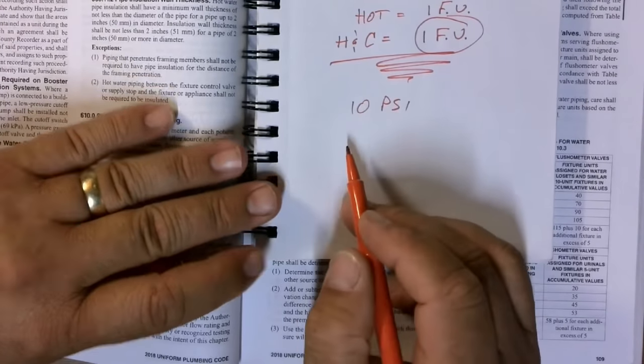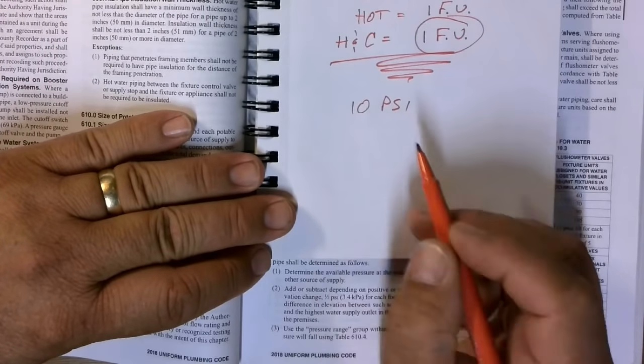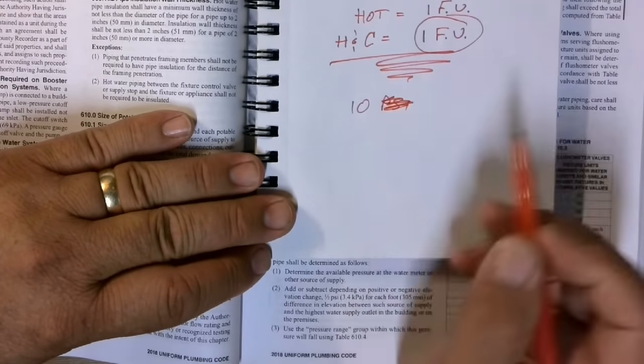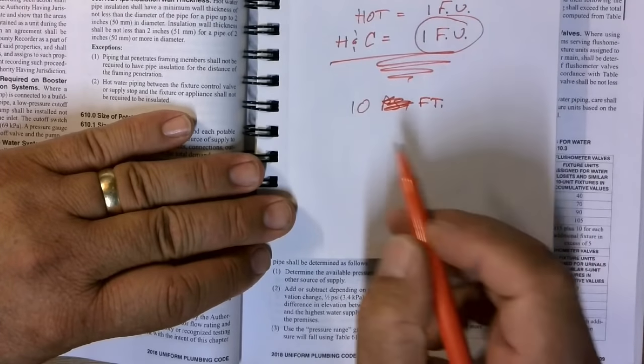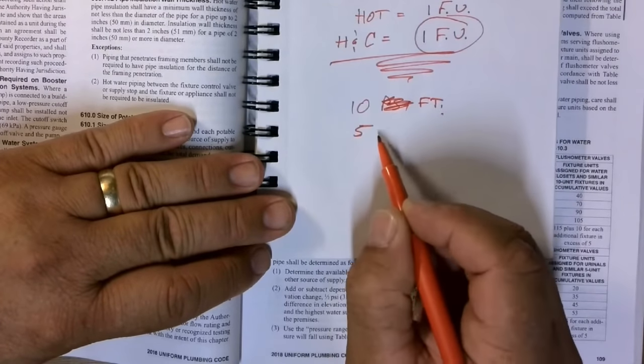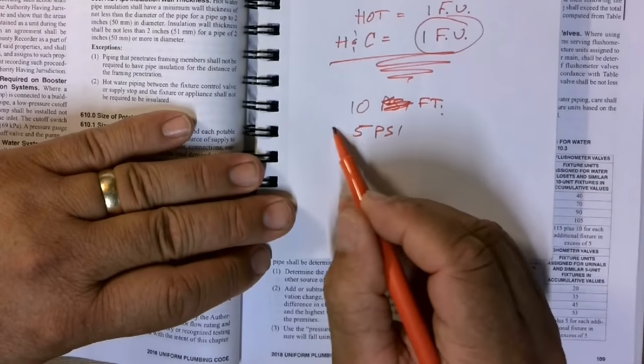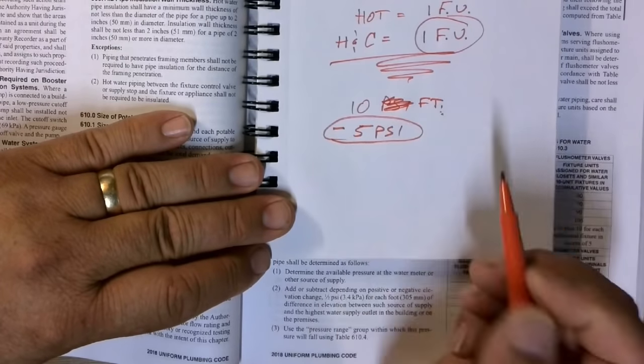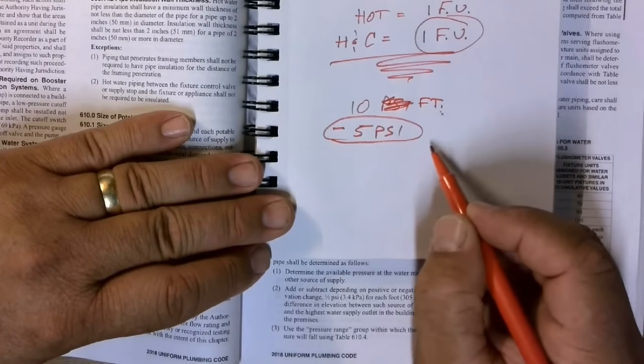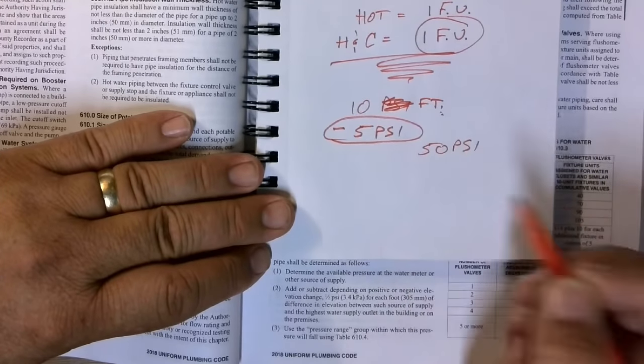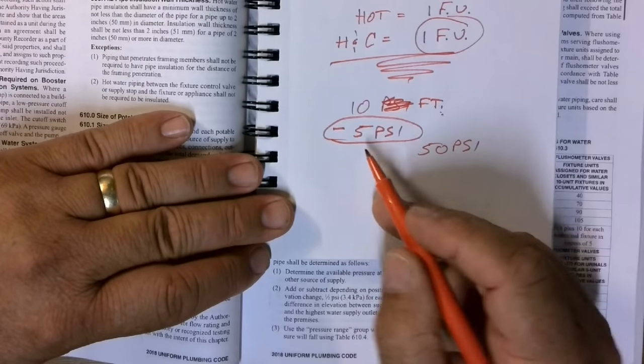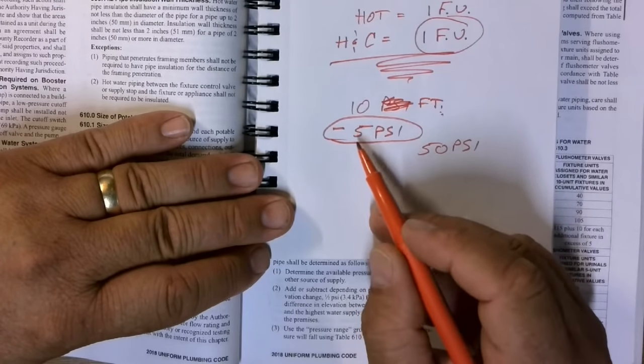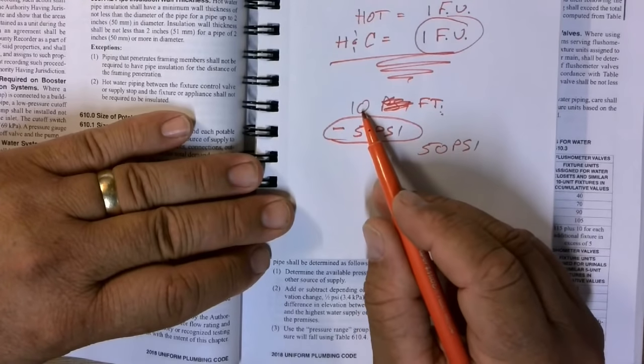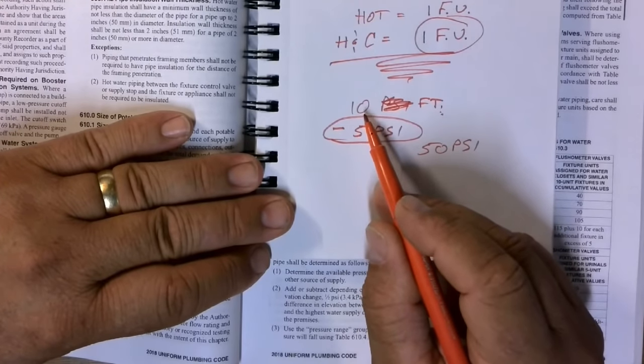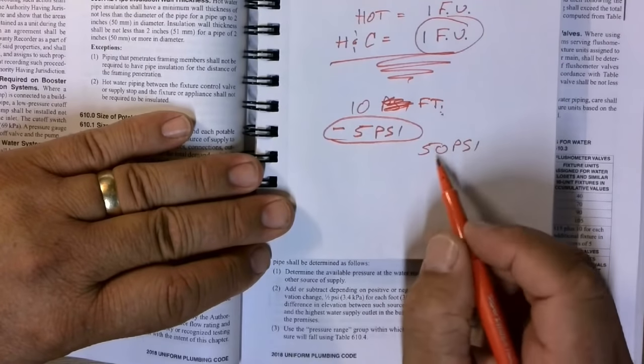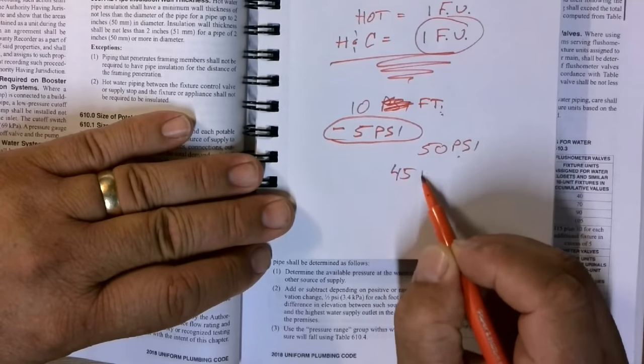Every foot, what they're telling us in this chapter, is we take half of this. So, I'm sorry, not 10 PSI, 10 feet. We're going to take half of this, and that's 5 PSI. So in 10 feet, we are going to lose 5 pounds of pressure. So if I had 50 PSI at the meter, I can only utilize, because it's taking that 5 pounds off, this negative 5 pounds is the 5 pounds necessary to get up to that 10 foot outlet. So if I start with 50, I end up with 45 PSI.